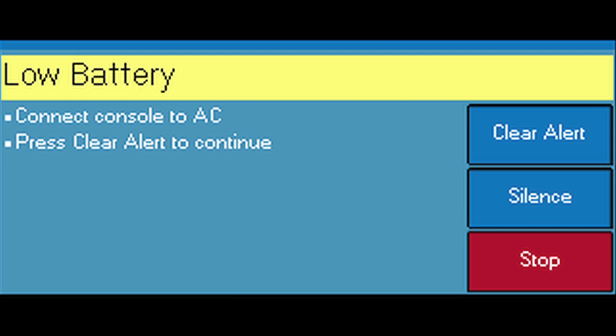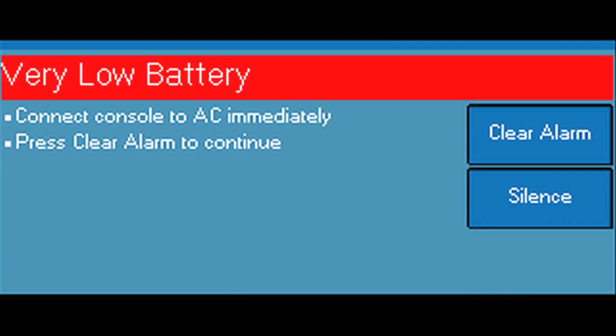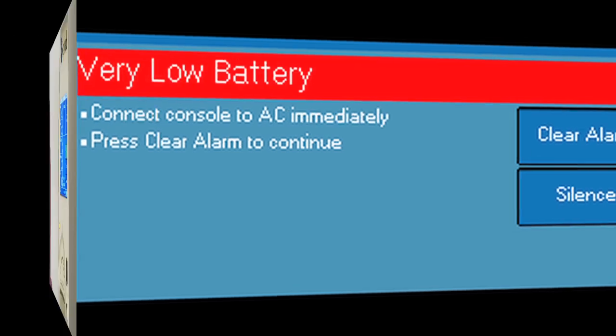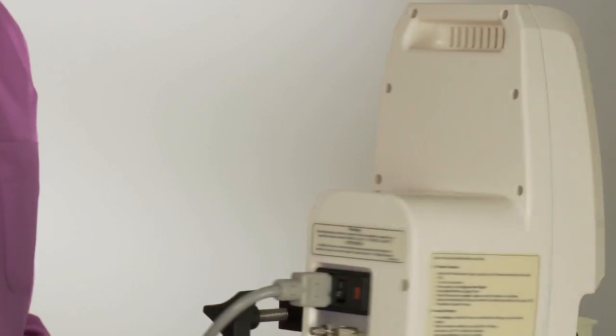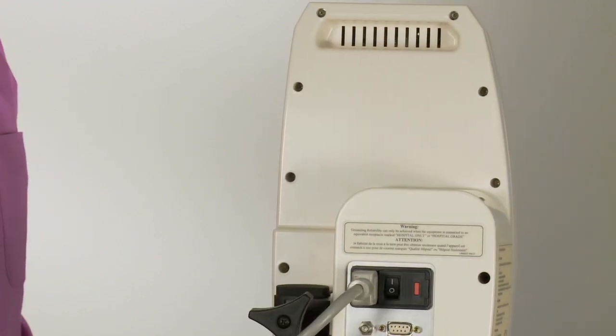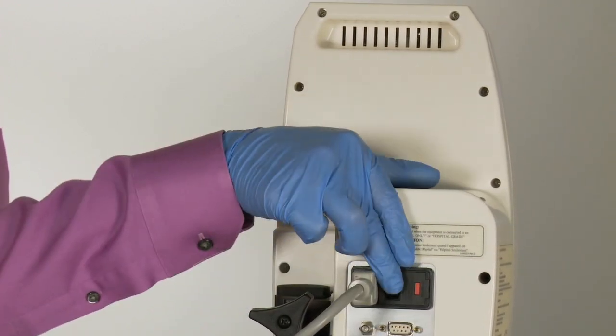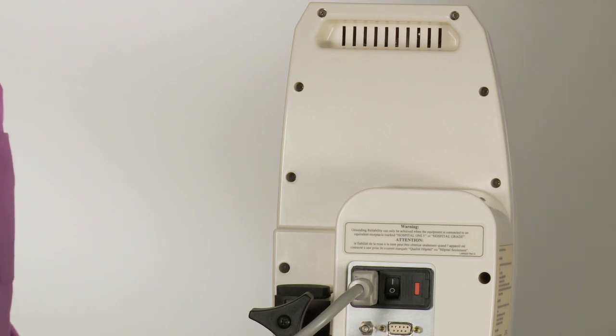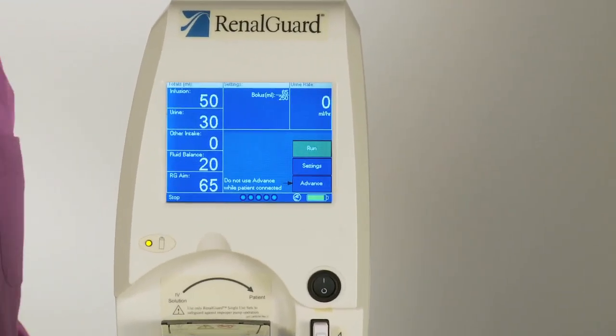If the console is not plugged in after 30 minutes, a low battery alarm will be displayed, and the pump will not operate until the power is connected. To charge the battery, plug in the console to a hospital-grade plug to ensure proper grounding. Also ensure that the switch on the back is on, the 1 position. When the battery is charging, the LED on the front panel will go on.